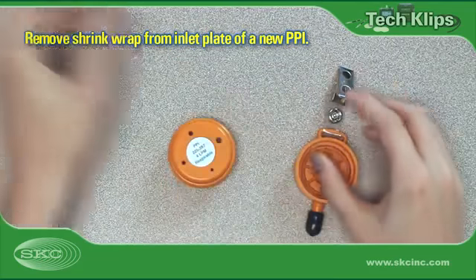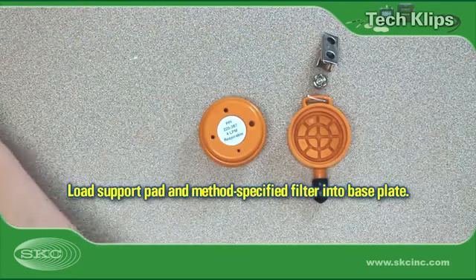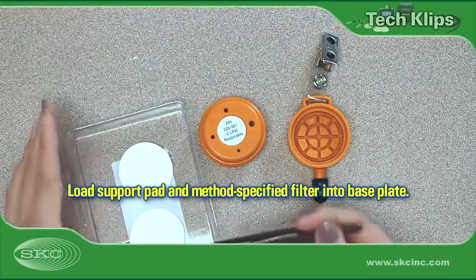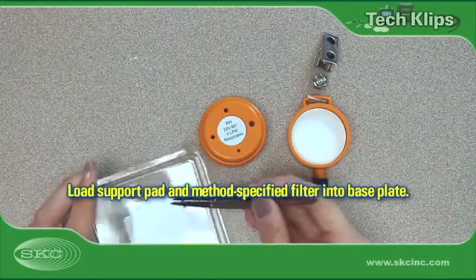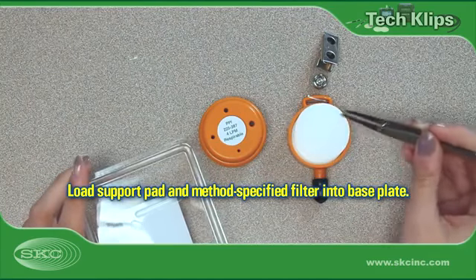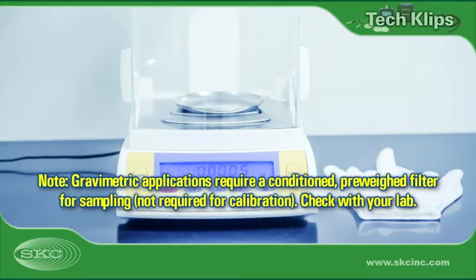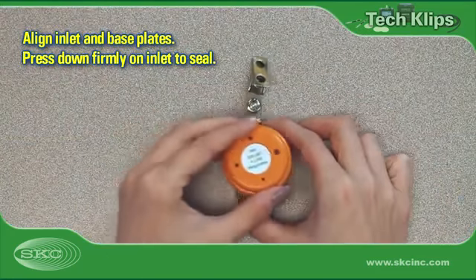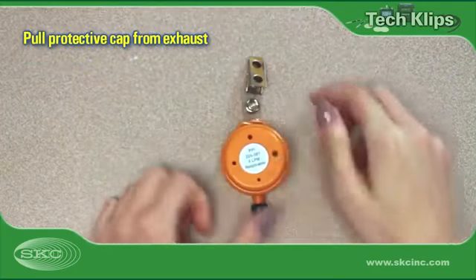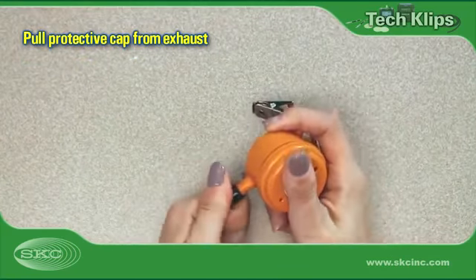This PPI model is supplied with a shrink-wrapped inlet plate. Remove the shrink wrap before proceeding. Use forceps to insert a 37 mm support pad and filter into the sampler baseplate. If you intend to sample for gravimetric analysis, you will need to have filters conditioned and weighed at a laboratory before sampling. Install the inlet on the baseplate. Press down firmly and evenly for an effective seal.